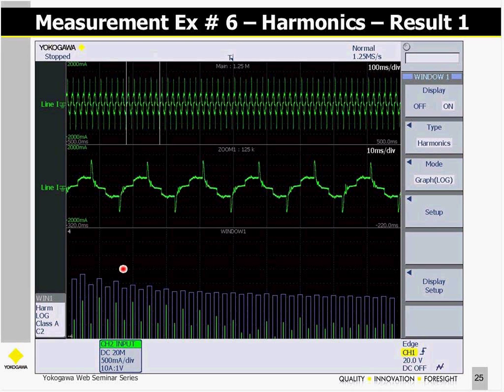After you do the harmonics analysis or the FFT, you can see each of the harmonics displayed as a green line here. I've got small odd and even harmonics, and large odd harmonics. The violet box here, the rectangle, is the template for pass-fail. If my actual measurement exceeds that violet box, then I violated the IEC 61000 standard for that test and for that class.